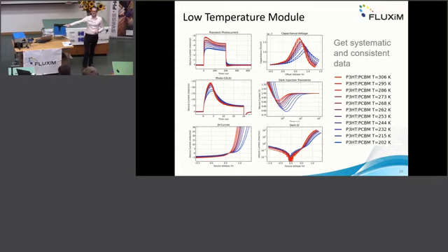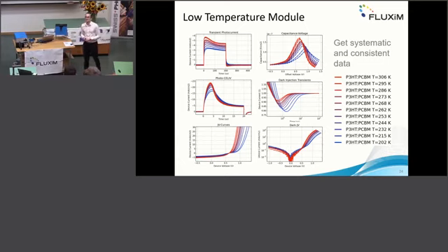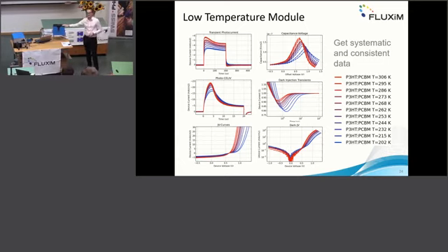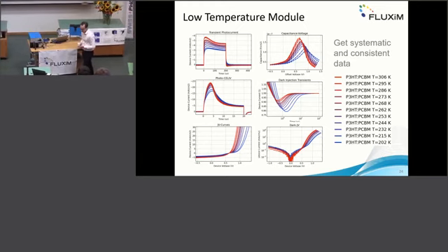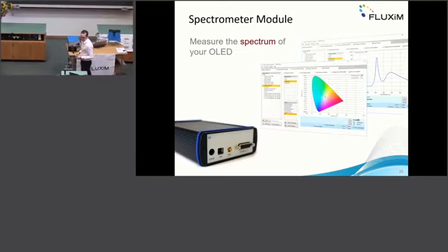And this here, the Peltier cryostat, you don't need to refill, because you only need to plug it onto the grid, and it cools by electricity. Of course, the drawback is that here you reach minus 40 degrees, and with liquid nitrogen you can go way below minus 100 degrees. Then we have implemented a spectrometer.